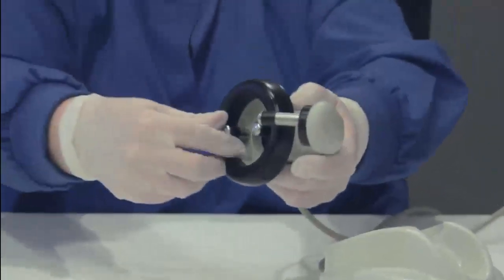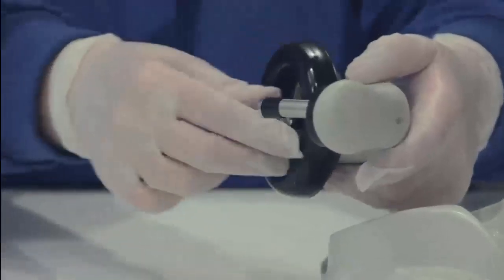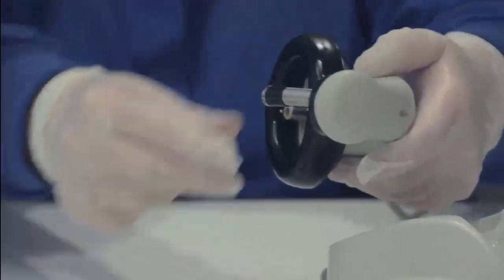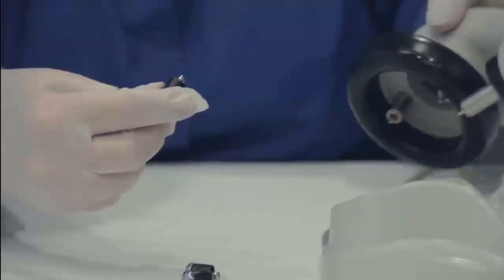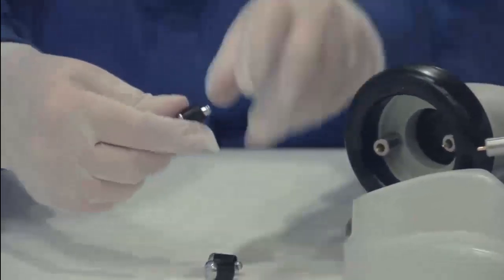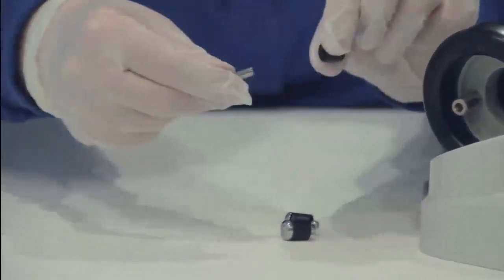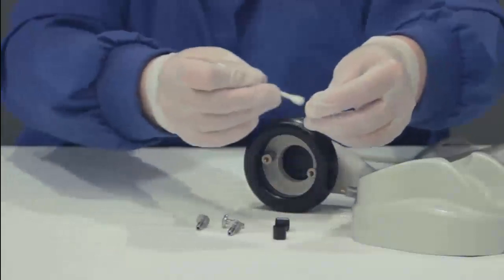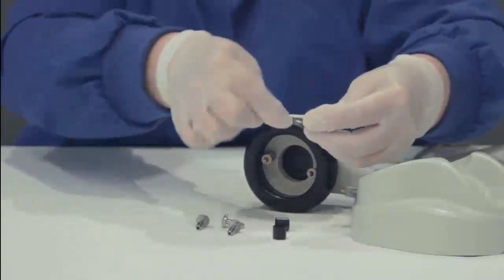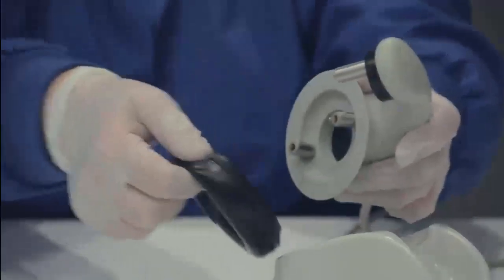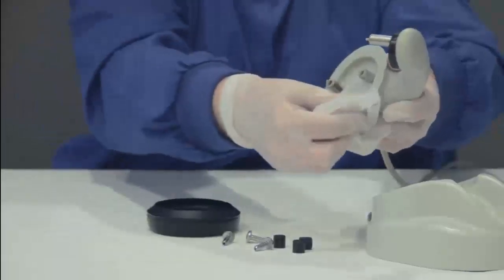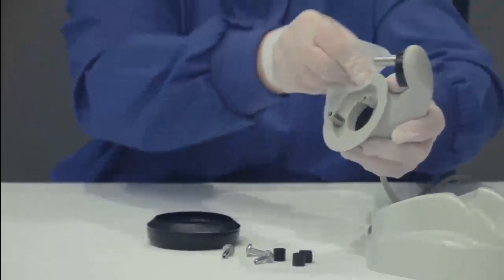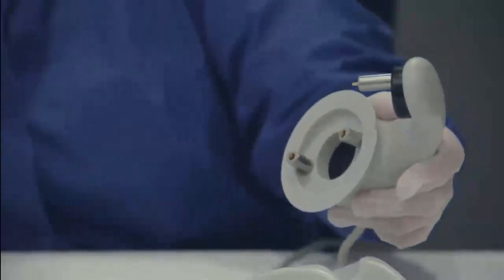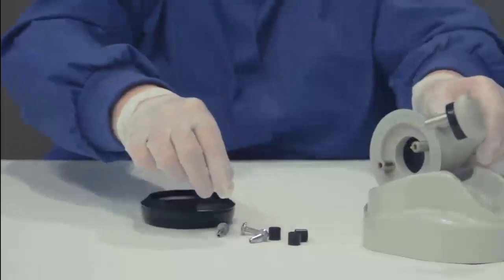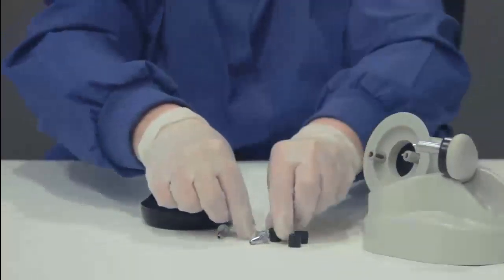On a regular basis, the electrodes should be removed from the BERAphone and inspected for the presence of gel buildup inside the black gel protector. The gel protector can be removed from the stainless steel electrode for more thorough cleaning. Additionally, the earphone cushion should be removed periodically for inspection and cleaning of the plastic under the ear cushion. When the components are clean and dry, reinstall them onto the BERAphone, making sure they're securely attached.